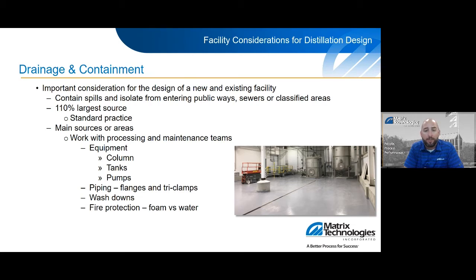The sources could include your equipment, that's your columns, your tanks, or your pumps, your piping connections, washdown areas, or CIP areas. And then back to fire protection, we talked about the foam versus water. Depending on which system you select, that's really going to be the driver of your containment footprint and size. So that's usually the governing factor for what you're getting into.